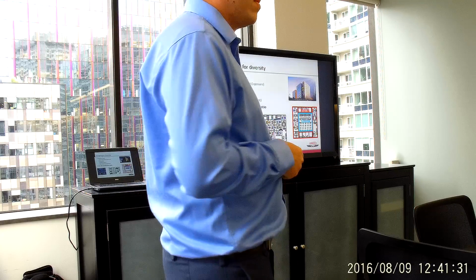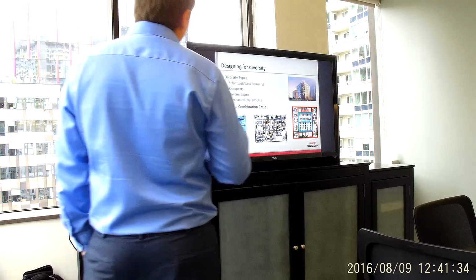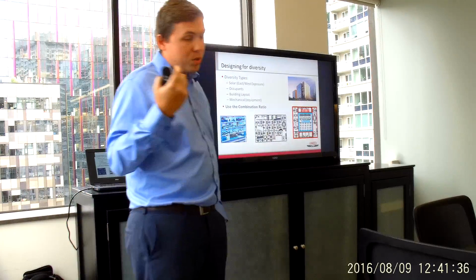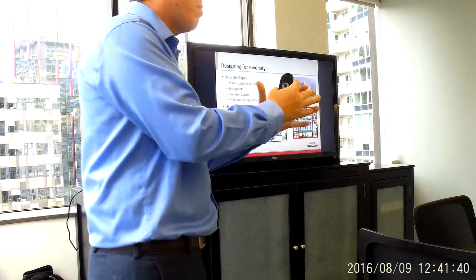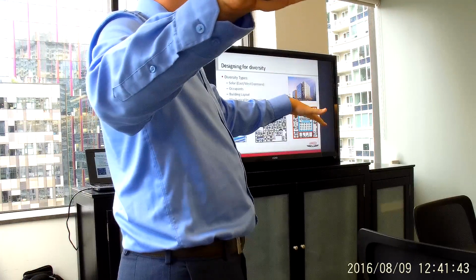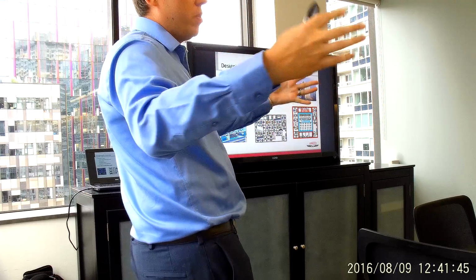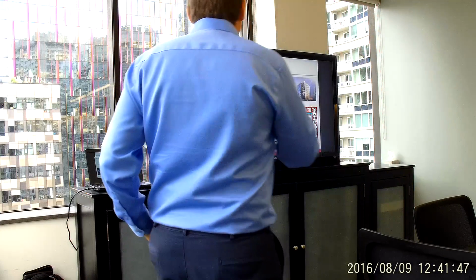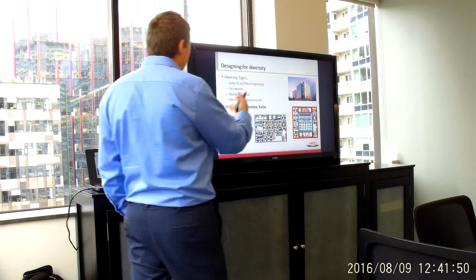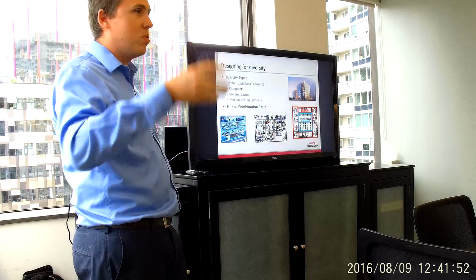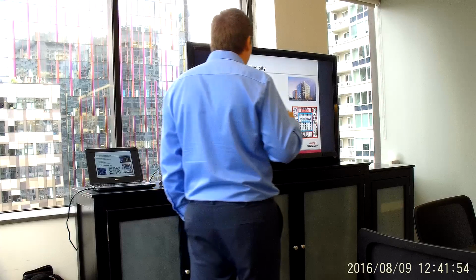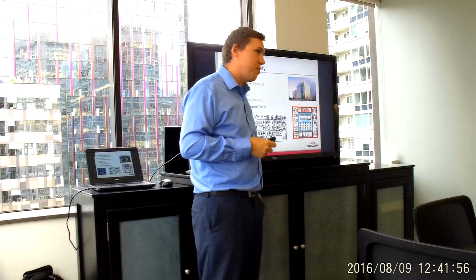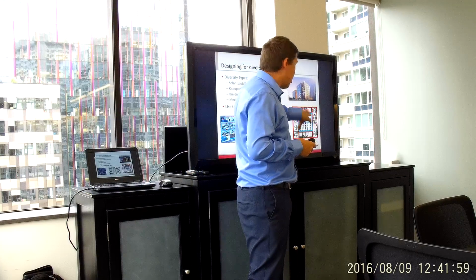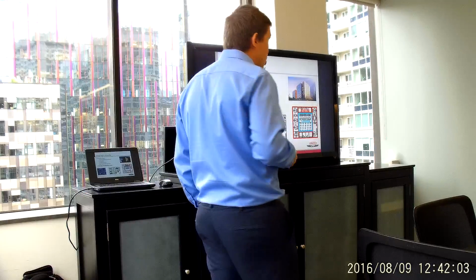Yeah. So, all right, designing for diversity on a VRF system, because we're looking at point loads and because we're addressing load where it exists as opposed to blanketly producing load or taking care of load on a floor by floor or large scale basis, we need to look at occupants, we need to look at building layout, all these things you know about. You guys have been doing it way longer than I have, so you know about that. But what's interesting is how you zone a VRF system. We try and zone as much internal and external together as we can for that heat recovery benefit associated with that.